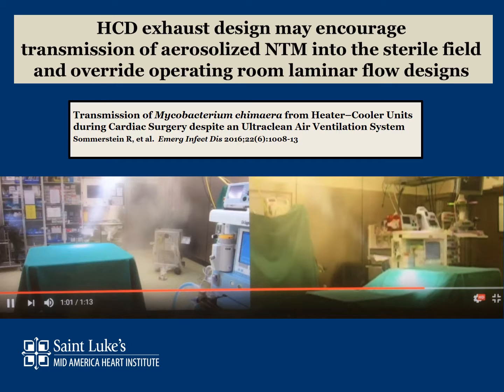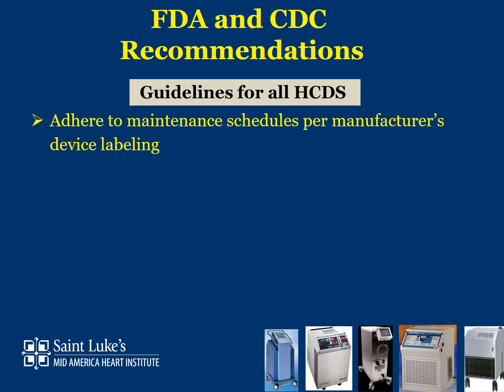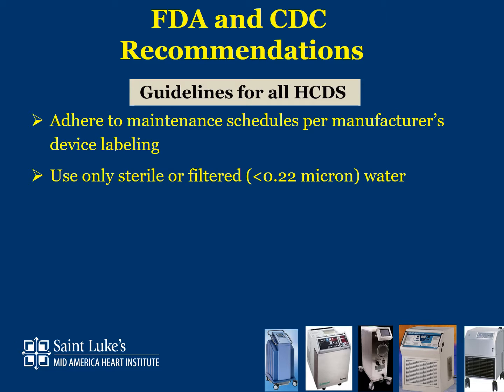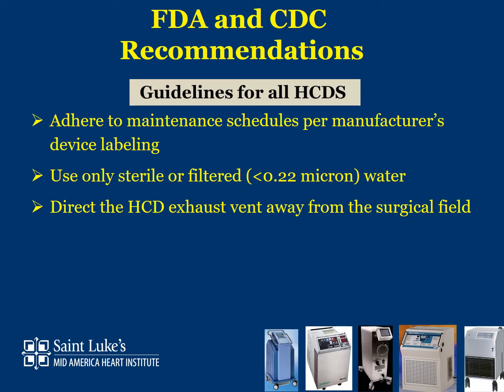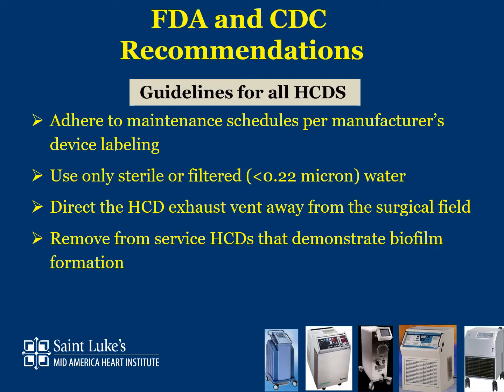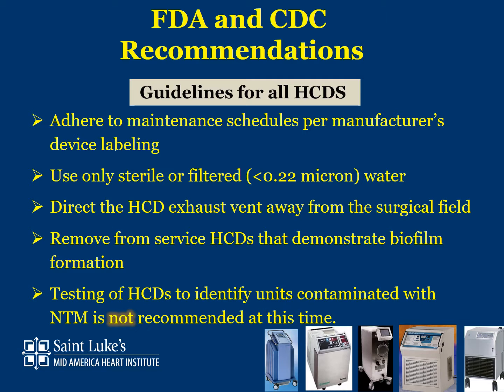The FDA and the CDC have some guidelines, recommendations for all heater-cooler devices. We need to adhere to maintenance schedules for manufacturers' device labeling, use only sterile or filtered water, direct the heater-cooler exhaust vent away from the surgical field and place the device as far away as we can, and remove from service any heater-cooler devices that demonstrate biofilm formation. One of the things that's not recommended is to test heater-cooler devices to identify units that are potentially contaminated.